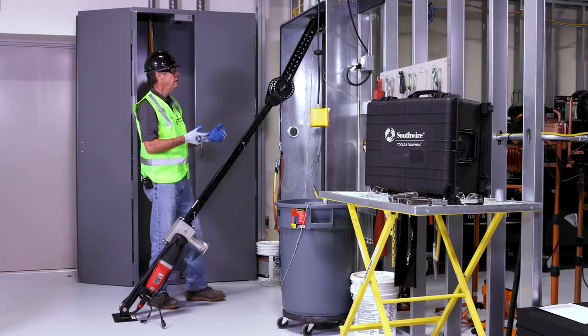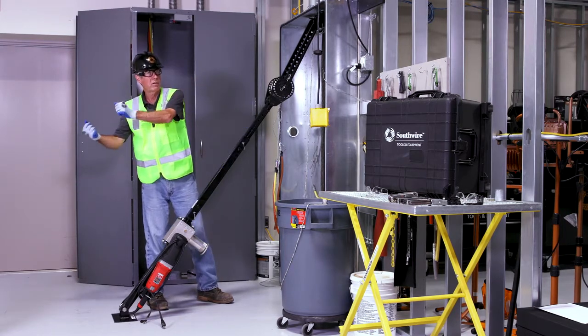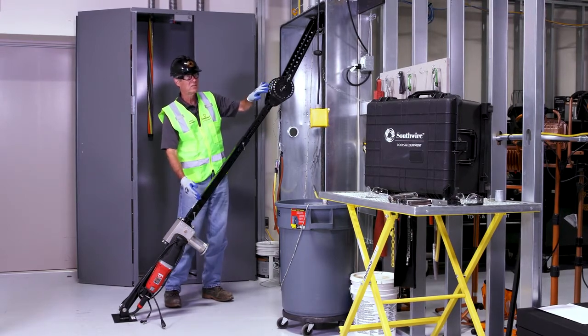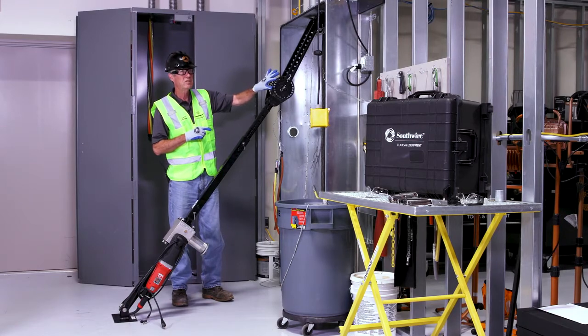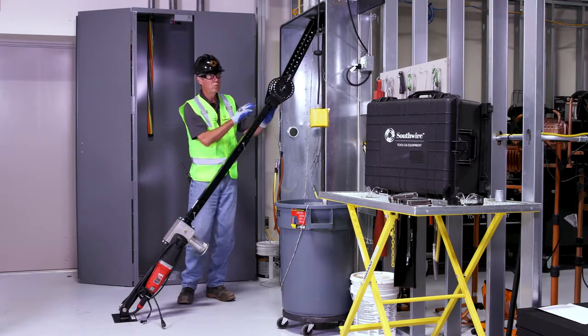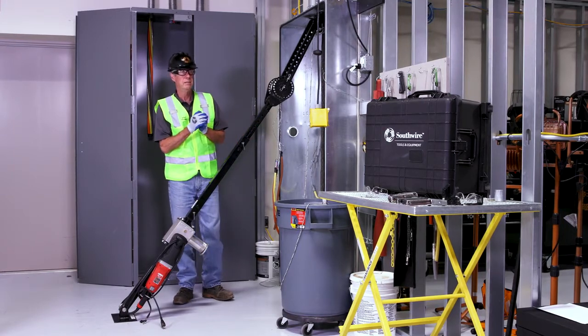So when I'm done, all I have to do is drop that half an inch and pull this out. A key element in doing this, when you're setting up your angles, you want to make sure the rope at least touches your roller before you engage in a wire pull. When the rope touches the roller, I am dead parallel to this bar and nothing will bend.